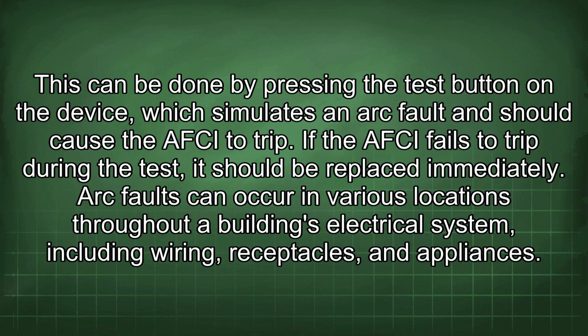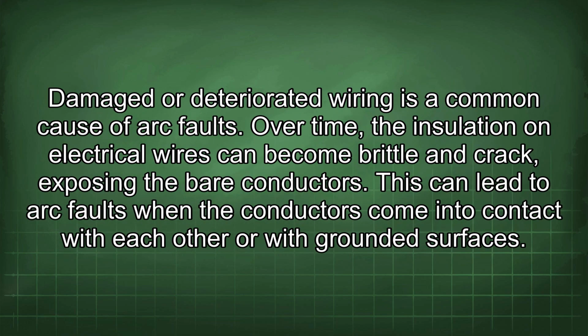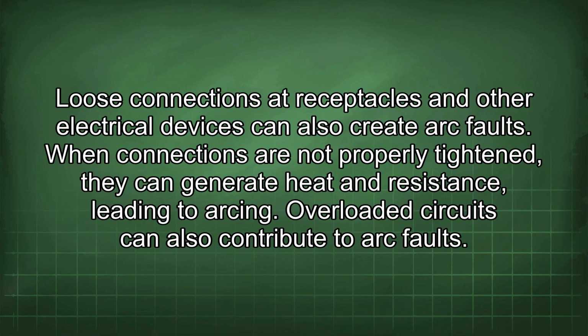Arc faults can occur in various locations throughout a building's electrical system, including wiring, receptacles, and appliances. Damaged or deteriorated wiring is a common cause of arc faults. Over time, the insulation on electrical wires can become brittle and crack, exposing the bare conductors. This can lead to arc faults when the conductors come into contact with each other or with grounded surfaces. Loose connections at receptacles and other electrical devices can also create arc faults. When connections are not properly tightened, they can generate heat and resistance, leading to arcing.